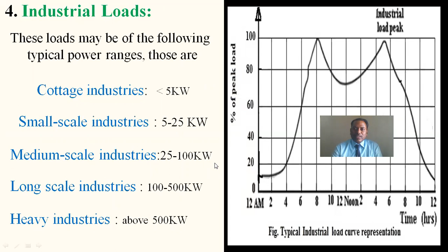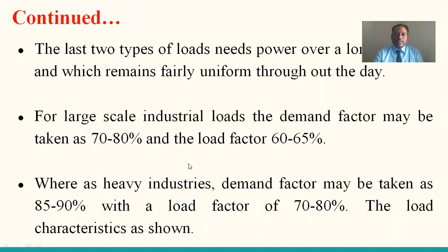We discuss the load factor and loss factor for various categories here. You can observe here, the last 2 types of loads need power over a long period. Heavy industries and large scale industries require a continuous long period of power which remains fairly uniform throughout the day. For large scale industrial loads, the demand factor may be taken as 70 to 80%, and load factor may be 60 to 65%. So see the impact of load factor. Out of 100%, around 60 to 70% of the power goes to the industries. Whereas for heavy industries, the demand factor may be taken as 85 to 90%, with a load factor of 70 to 80%. The load characteristics were already discussed in the earlier slide.